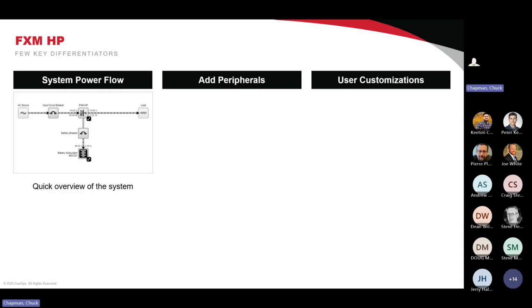So it has a line mode where it's effectively super efficient, just connecting the input to the output. But if the voltage falls very much, it'll go into a mode called boost. There are two forms of boost, and it can boost and maintain the range of output voltage, like 108 to 120 over 85 to 120 volts. Then on the other side, there's a buck system, another set of two taps that allows it to go up to 150 plus volts. All it does is change the taps and keep the output right around 120. It's remarkable, and the system is very easy to use.